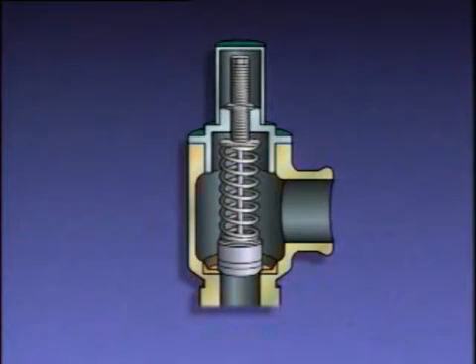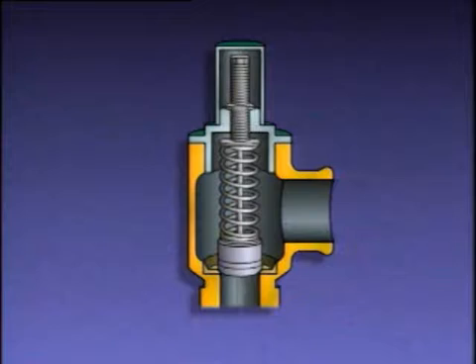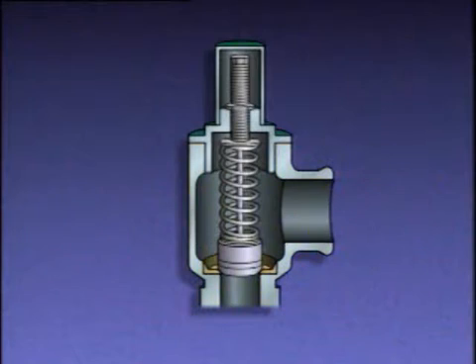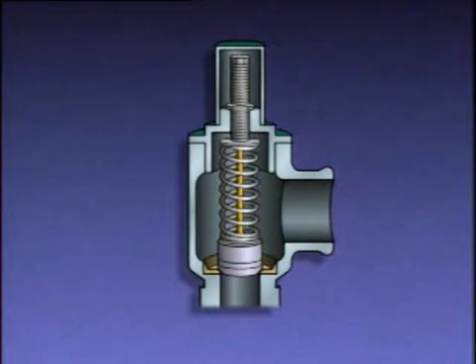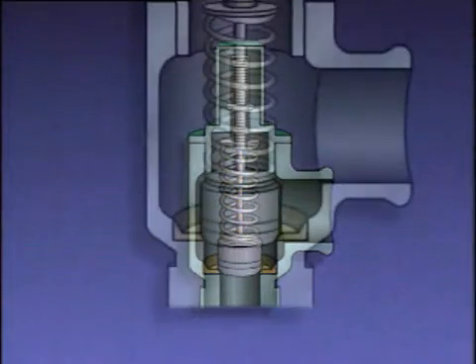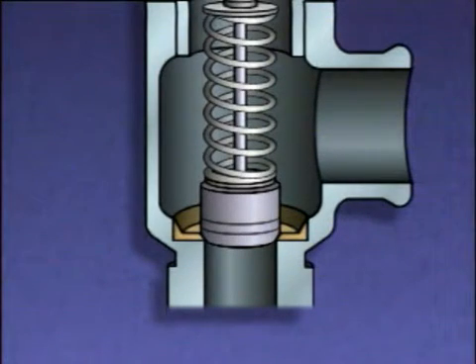The valve body or casing provides a path for the liquid to flow and holds the other valve parts in their proper positions. This is the valve's inlet, and this is the outlet. The disc rests on the seat and is held in place by the spring when the system is at normal pressure. The valve stem guides the disc up and down, just like in other valves. A relief valve is set to open when the pressure in a system reaches a predetermined value, say 200 PSI.